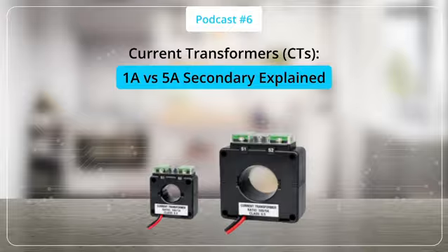Now, let's understand how to select the right CT secondary rating. The first factor to consider is distance. For long-distance connections, 1A is generally the better choice. Next, consider the cable type. Thicker cables work better with 5A for short distances, while thinner cables are more efficient with 1A over longer distances.